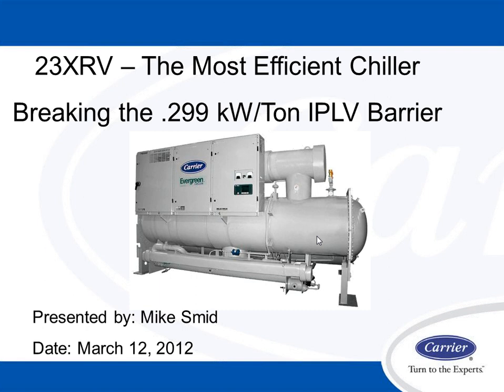What we're going to do next month is take this machine and show how going from parallel to series counterflow, we can improve the efficiency on this particular machine. Even though it has fantastic efficiencies at full load, in parallel, we could put it in series and improve the efficiency 10 to 15%. That would be greater than 50% better than the ASHRAE minimums in some cases. So it's a huge opportunity.